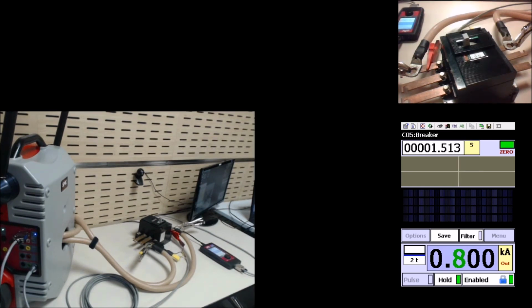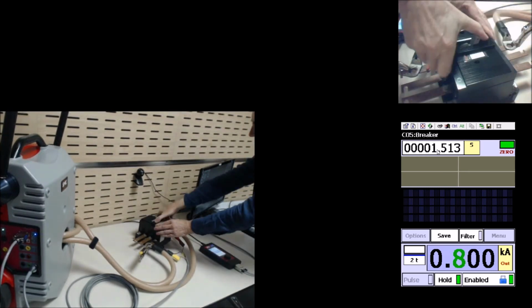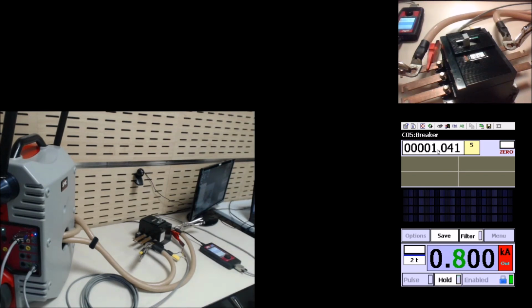You have possibly heard the starting of the magnetic element in this breaker. Also, the trip time is not magnetic. This is a thermal trip time. Magnetic time is much smaller, a few tens or hundreds of milliseconds. This is still in the thermal section of the curve. Let's try again. You see approximately the same time here. And let's go to 900. 900 is supposedly, let's check the curve again, well inside the magnetic section. So let's try there.